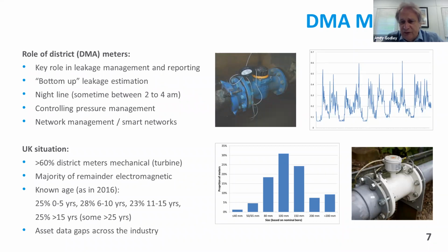But you can also see about halfway along that trace, that minimum flow goes up slightly, which could be indicative of a leak. But it could also be indicative of a problem with the meter. Which is again another reason to understand meter accuracy. In this case, it's fairly clear cut because the change is fairly sudden, but in other cases that change can be much more gradual, and it can be much more difficult to understand whether it is a metering problem or whether it is a genuine leakage problem.